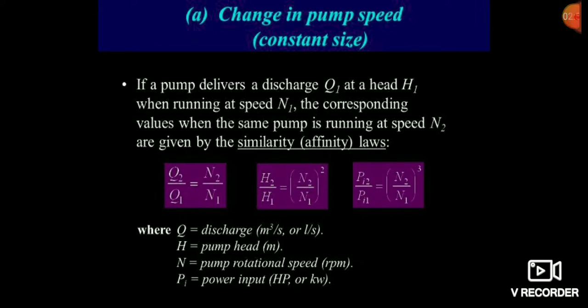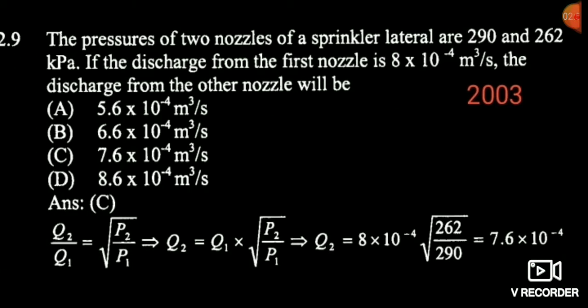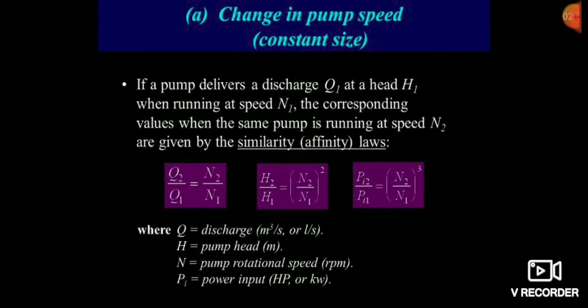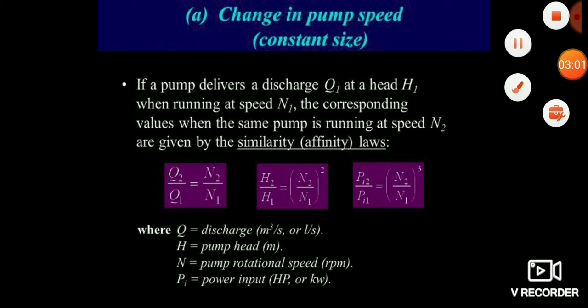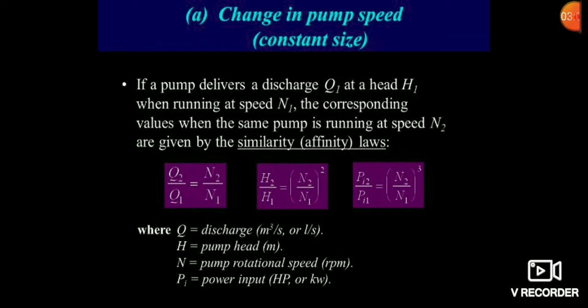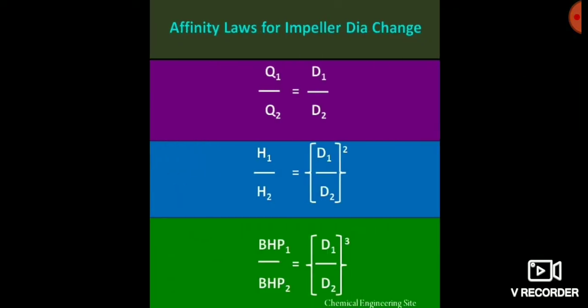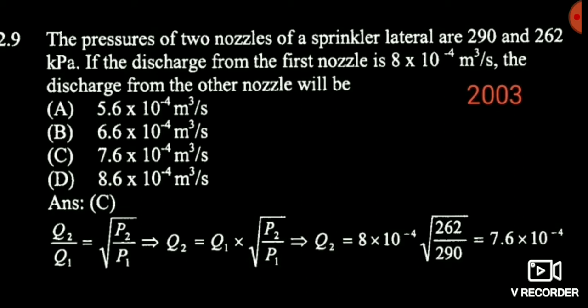Q2 by Q1 equals a pressure relationship. H2 by H1 is equal to N2 by N1 squared. And since N2 by N1 is directly proportional to Q2 by Q1, we can conclude that H2 by H1 is proportional to the square of Q2 by Q1. Here the speed is not given, but the discharge is given, and we know that speed is directly proportional to discharge.